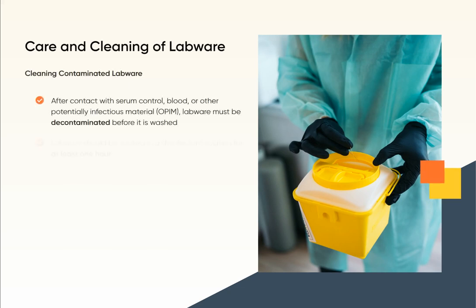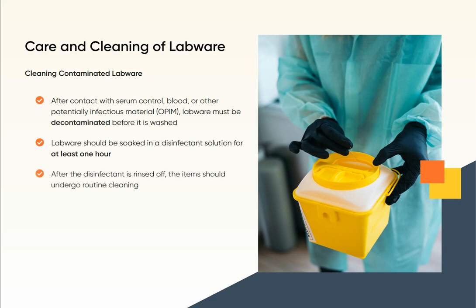After contact with serum, blood, or other potentially infectious material (OPIM), labware must be decontaminated before it is washed. Labware should be soaked in a disinfectant solution for at least one hour. After the disinfectant is rinsed off, the items should undergo routine cleaning.